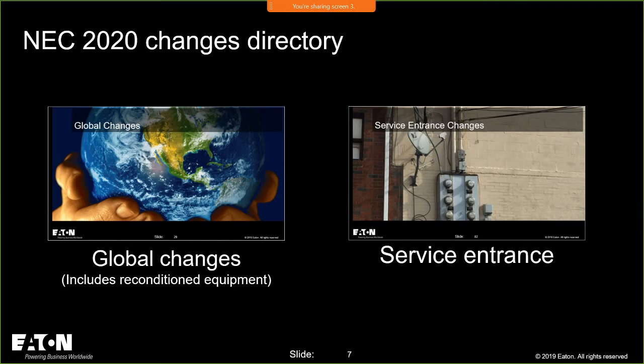And you'll see it in 220. In Article 220, I love this. People, I've had this debate with individuals, and if you look at Article 220, 220.12a talks about lighting load for non-dwelling occupancies. There's an informational note, I love this: the unit values of Table 220.12 are based on minimum load conditions and 100% power factor, and may not provide sufficient capacity for the installation contemplated. So we say it right in the code that if you follow this and do this calculation, it might not be enough capacity. So it's an important thing to remember.